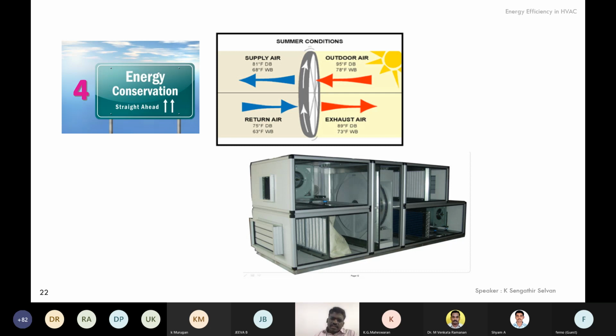instead of directly bringing in the fresh air, what we can do is use the residual cooling energy in the exhaust air. Now, what is exhaust air? In a bottle of water, if you want to add fresh water, you have to drain some water anyhow in order to bring in more water. So this exhaust water is equivalent to exhaust air. You need to exhaust a small amount of air. We are going to exhaust the cold air to the ambient, but we are going to use that cold air to pre-cool our fresh air.